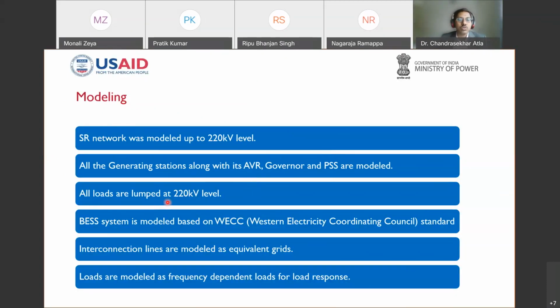And the loads are lumped at 220 kV level, and most importantly, the analysis is targeted for the battery energy storage system. Hence the BES model, which suits the dynamic stability study, has been adopted from the WECC, Western Electricity Coordinating Council, standard, which has been published in CIGRE, to model the BES. Interconnection lines with the other regions have been considered as equivalent grids. Like the southern region is connected with the eastern region and western region, so those have been considered as equivalent grids. As Dr. Nagaraj sir has mentioned, loads and their load response have been considered with reference to frequency dependent load, so that the load response has been captured for the primary reserve analysis.